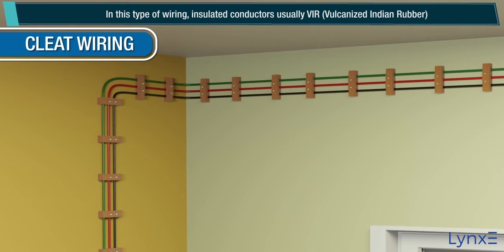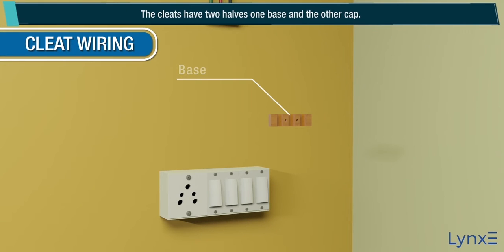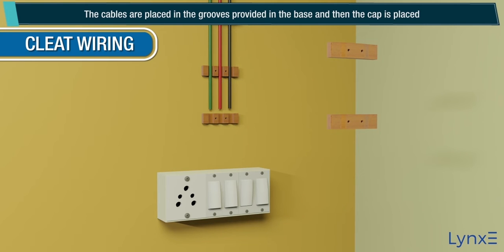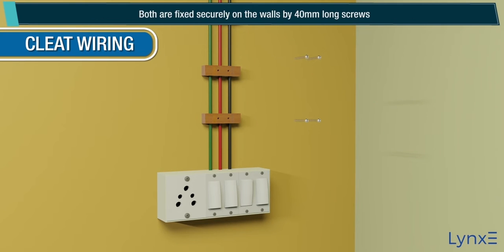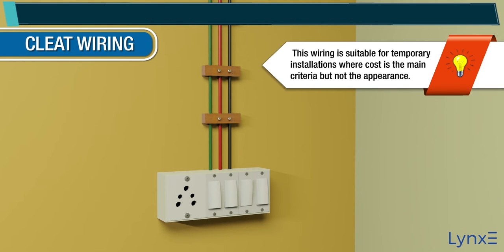Cleat Wiring: In this type of wiring, insulated conductors, usually VIR (vulcanized Indian rubber), are supported on porcelain or wooden cleats. The cleats have two halves — one base and one cap. The cables are placed in the grooves provided in the base, and then the cap is placed. Both are fixed securely on the walls by 40mm long screws. The cleats are easy to erect and are fixed 4.5 to 15 centimeters apart. Note: This wiring is suitable for temporary installations where cost is the main criteria but not appearance.